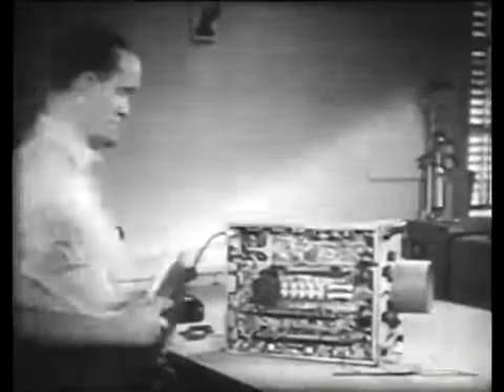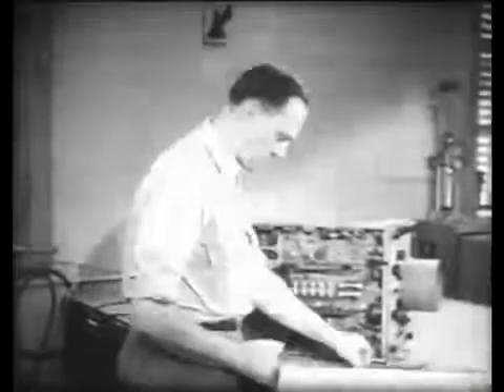You must make sure that the equipment is completely de-energized. The large capacitors, which you can locate in the diagram of the equipment, may still be a source of danger. Even if the device is equipped with bleeders to drain off the stored-up charges, safety demands that all of the large capacitors be located and discharged. There's a risk that some of the capacitors may be overlooked due to their resemblance to other components.